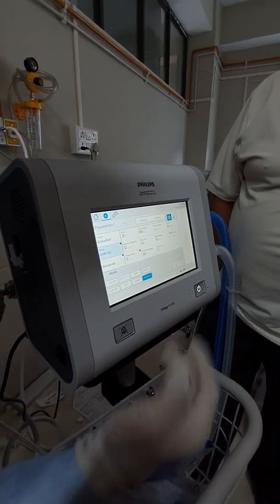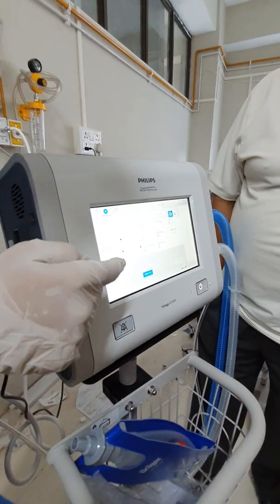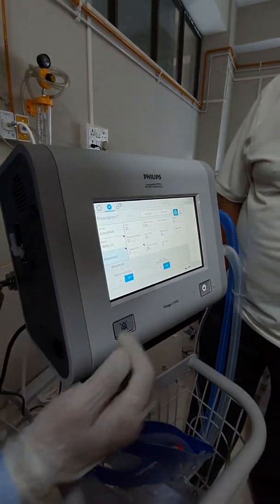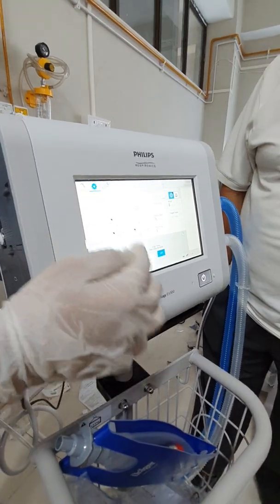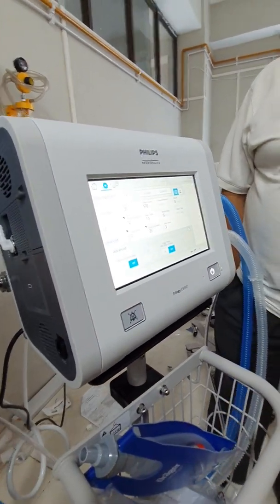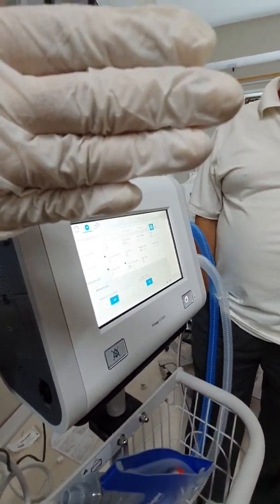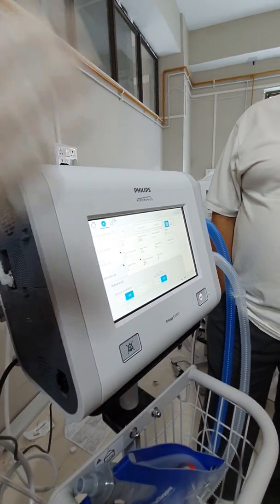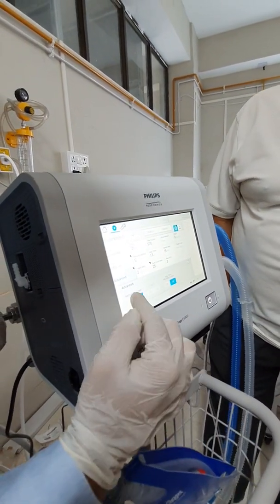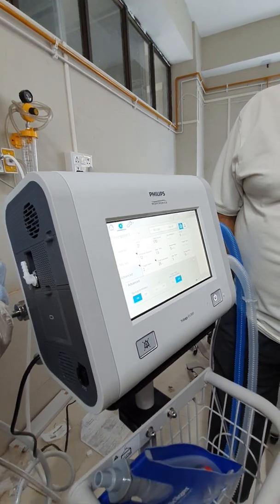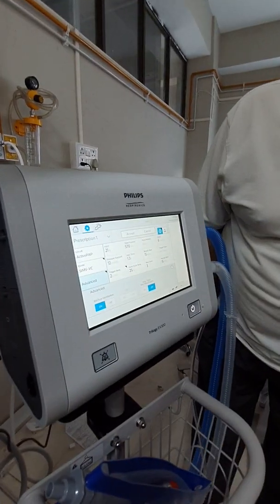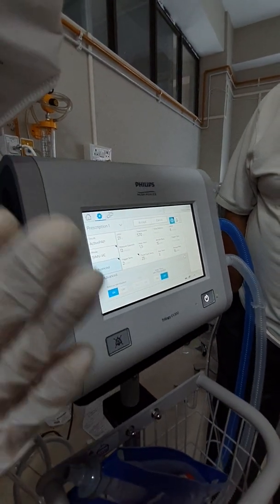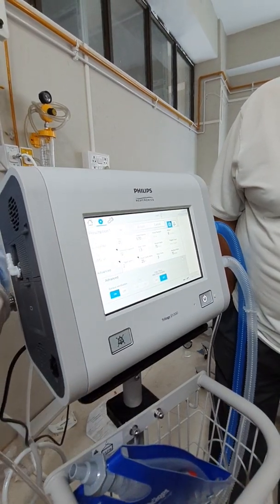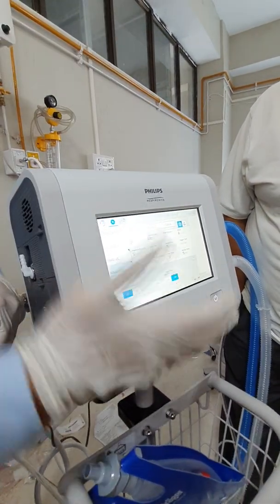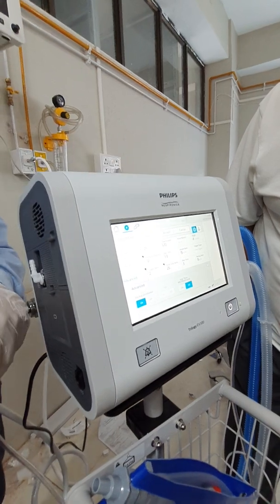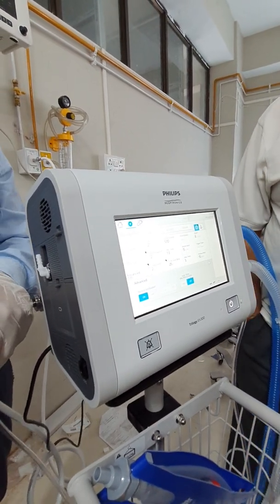Modes like ACVC, SIMV. Here, going to advanced, there is a backup ventilation. So please remember, when you are in a spontaneous mode like ST, CPAP, SIMV, please make the backup on. But nowadays they say that SIMV should be stopped; we should not usually go for SIMV. But we have to give it because it's an FDA approved product, and as per the FDA protocol you have to have all the modes.